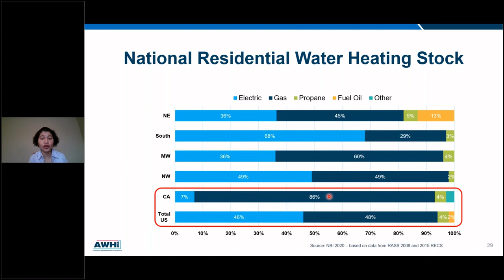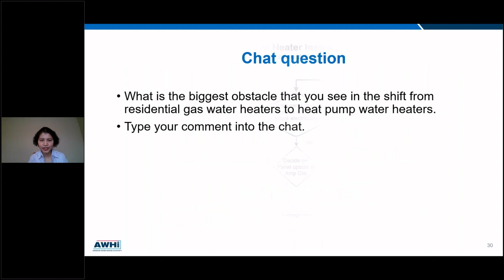Going back, there's a big percentage of customers on fossil fuel water heaters, and for those customers, if they want to decarbonize, the only option currently is expensive and extensive panel upgrades. If you're replacing a gas water heater with an electric water heater, typically you have to spend $1,000 to $3,000 for panel upgrades because you don't have a 240 volt outlet available right next to the water heater.